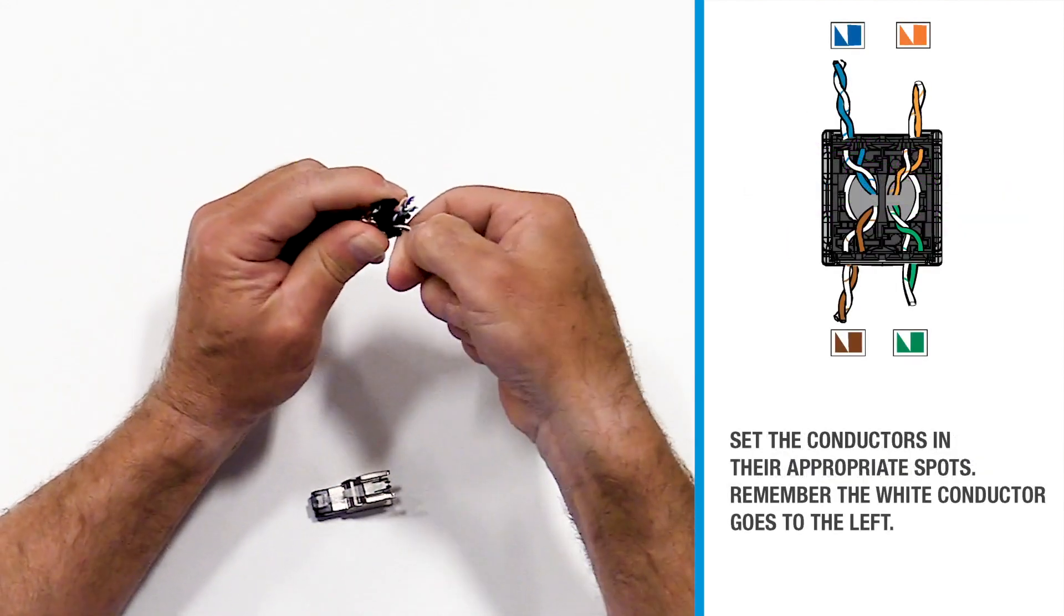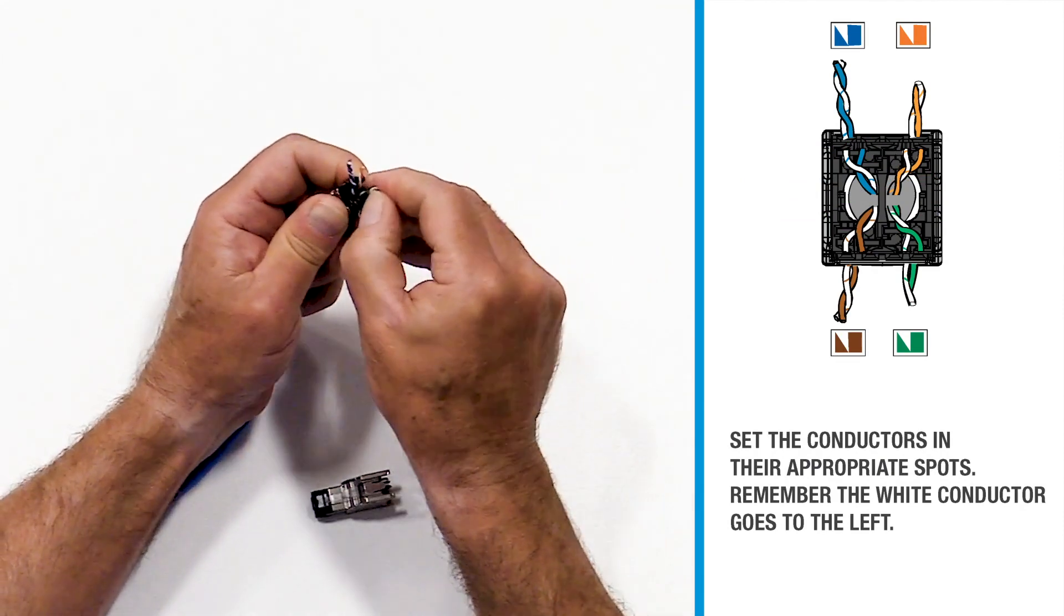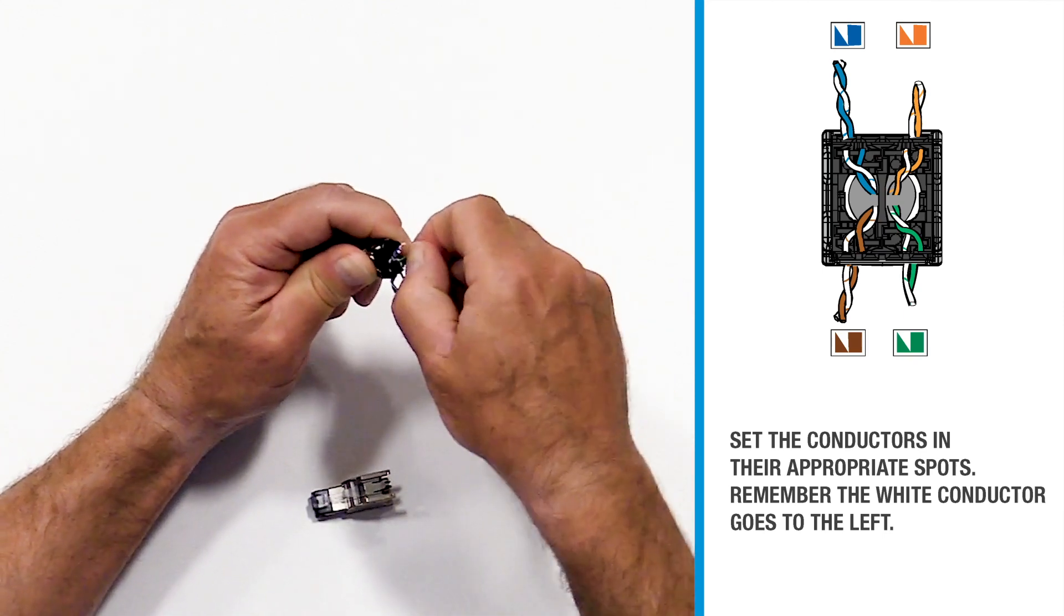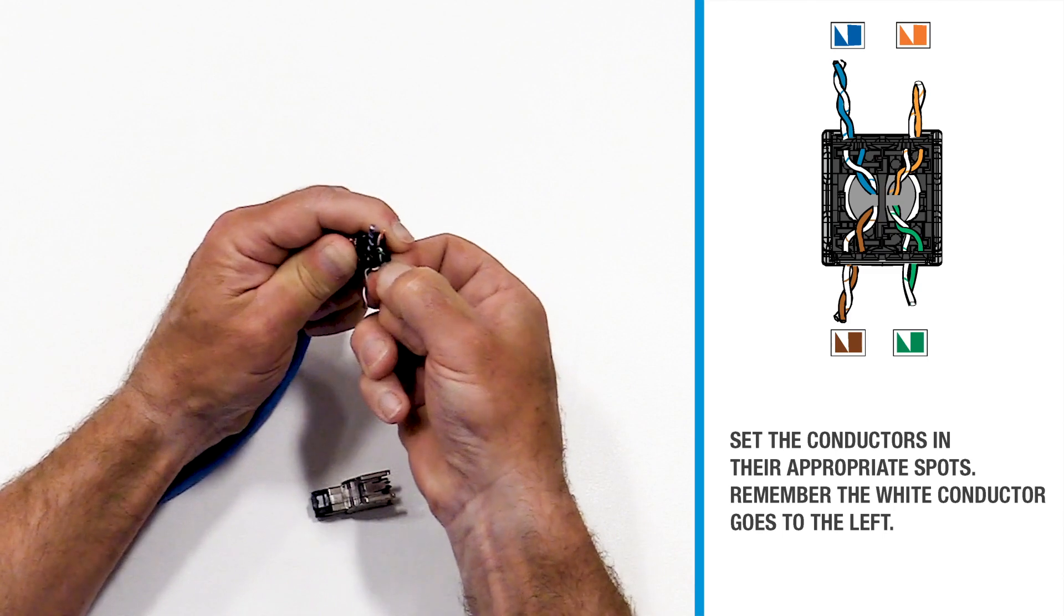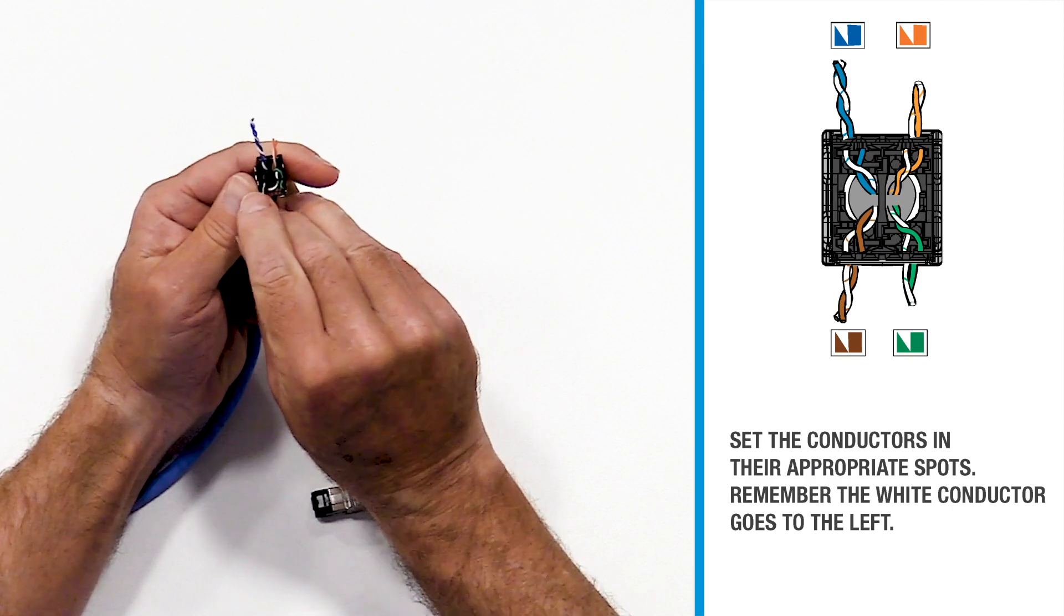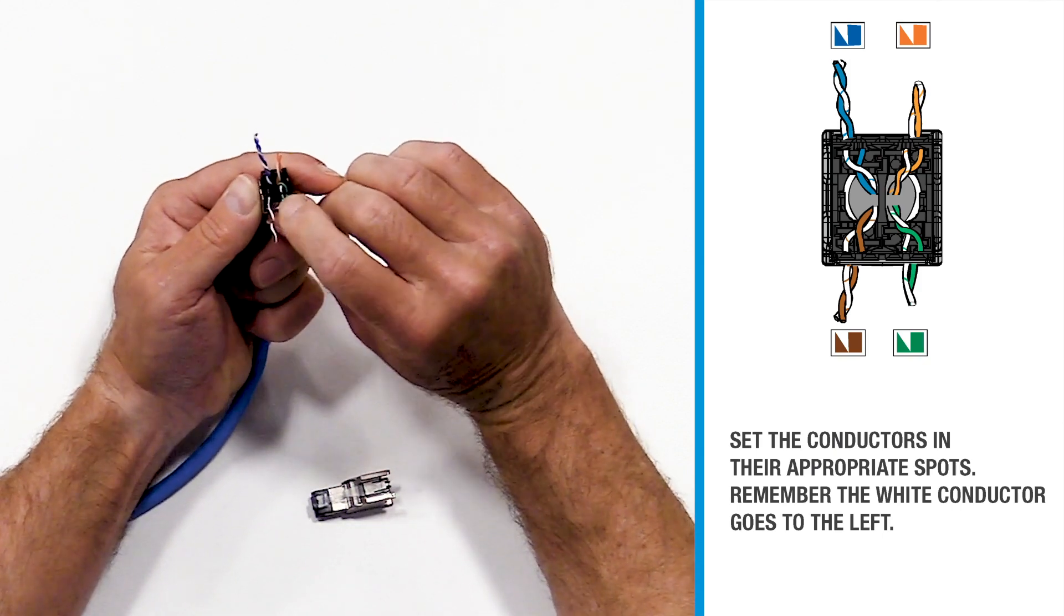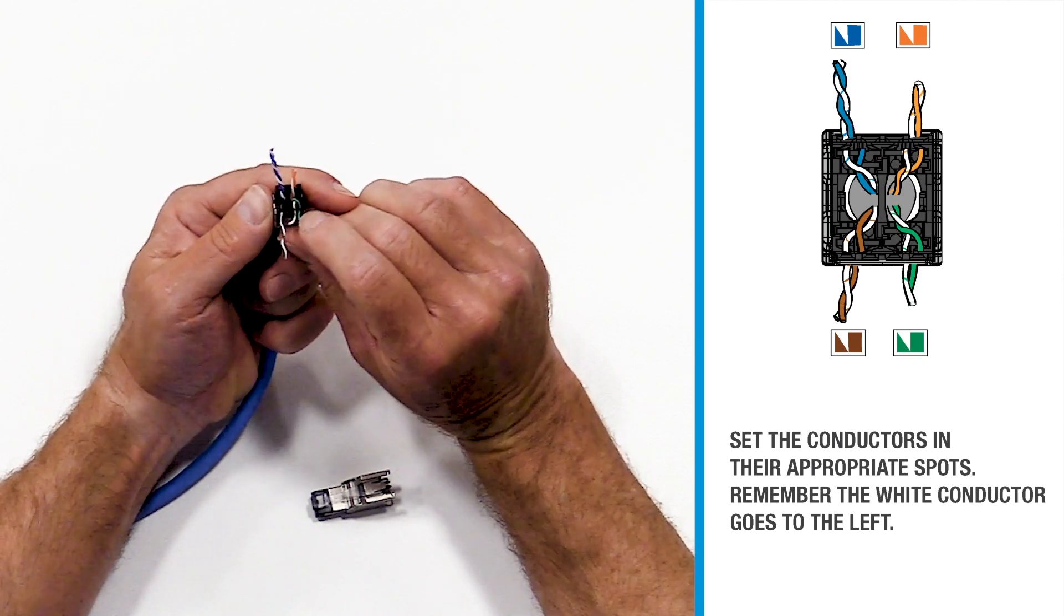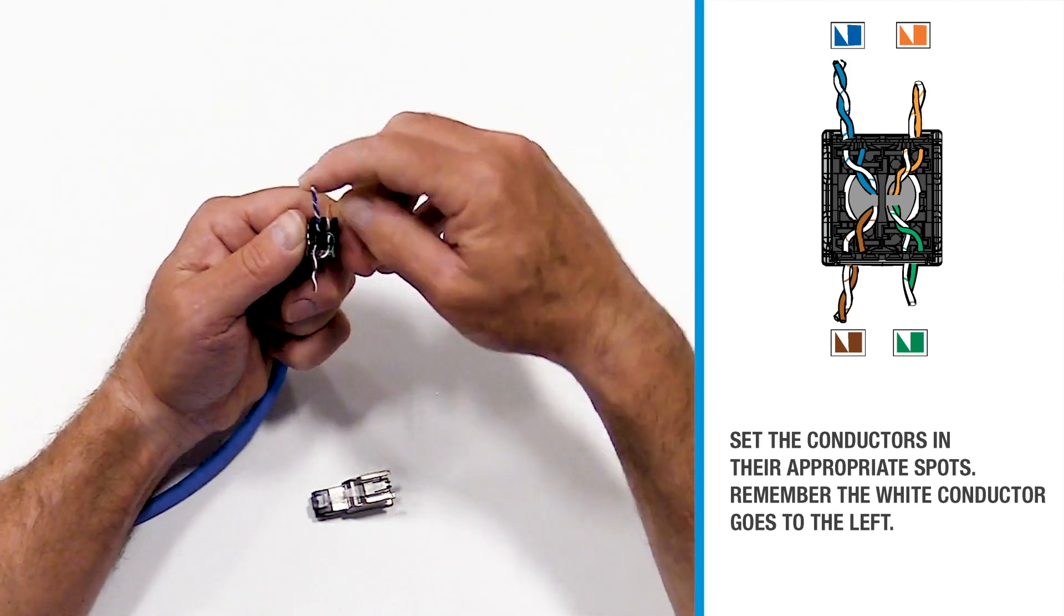Set the conductors in their appropriate spots, always remembering that within the specific quadrant, the white conductor always goes to the left, the solid conductor will always go to the right. The white conductor of the brown pair goes to the left, the brown solid conductor goes to the right. The white conductor of the green pair goes to the left, the solid green conductor goes to the right.